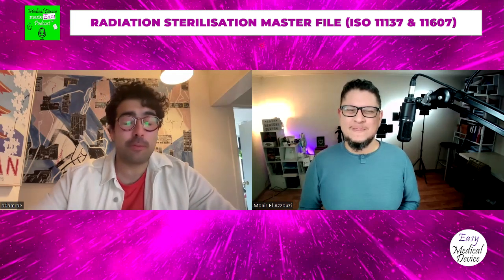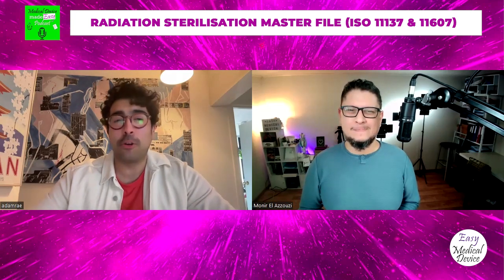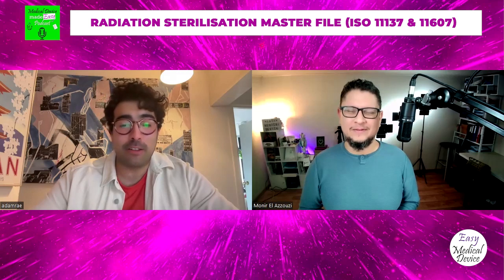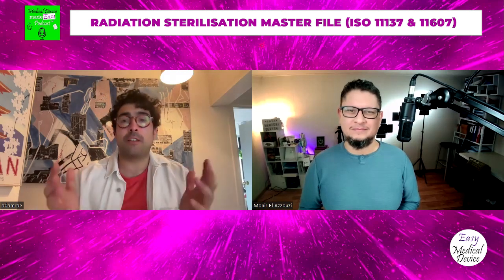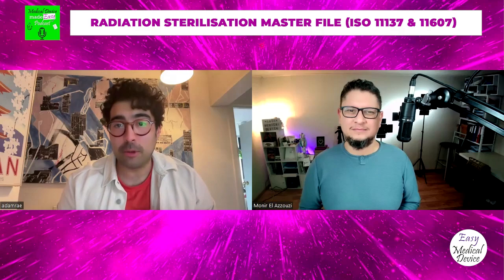That is quite true, for people not working in it, I suppose. For us, harmonized standards are essentially standards that have been recognized by the Commission as saying you can apply this standard. This is the standard that should be used as part of conducting, in this case, sterilization. ISO 13485 is a harmonized standard that should be used to implement your quality system. There's a massive debate, you've seen it, I've seen it, on whether you need to use a harmonized standard or not.